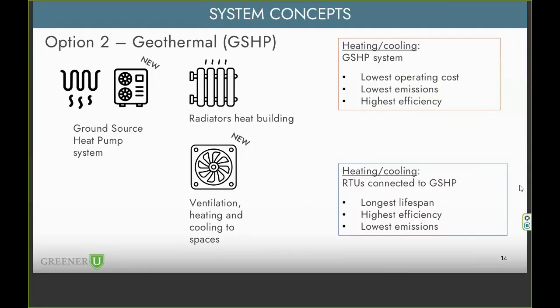The second option was the geothermal ground source heat pump idea. It has the lowest operating cost and highest efficiency, using rooftop units similar to the air source heat pump option for heating and cooling, but now you don't need the natural gas boiler because you're getting heat in the winter from 55-degree earth rather than 10-degree outside temperature. That's what makes geothermal much more efficient, and arguably more expensive because you're drilling wells.